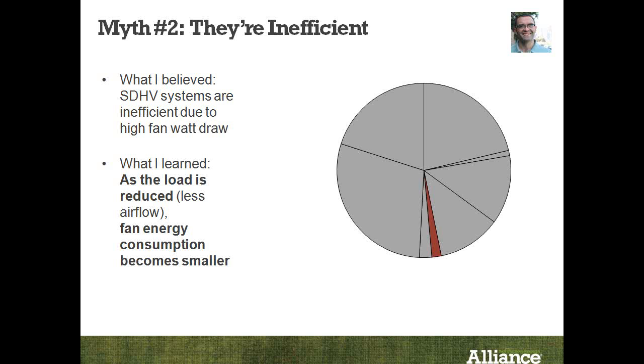So we have 3 different ways that we've looked at the airflow. We measured it at the lab house using a black felt test. We measured it in our laboratory with a hot wire anemometer and a duct blaster, and we measured it using CFD analysis. All of our evidence supports that there's very good throw from a small diameter duct, even at very low airflows. So let's go on to the second myth and deal with this one.